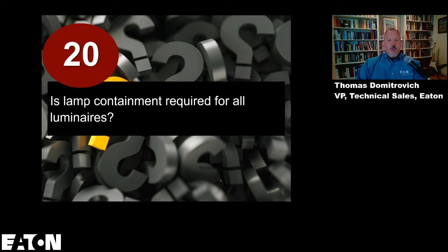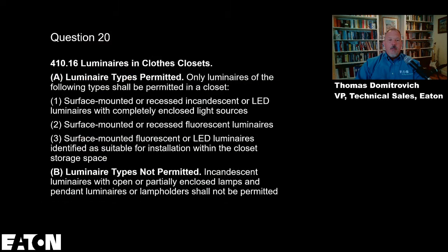And it's not required for all luminaires, but I guess the message is, it depends on where you're applying it, right? The location that it's being applied. If it's in a hazardous location, obviously there are going to be containment issues. If it's in that sporting arena, which is a previous question, there are containment items. If you're in an area where you're near fabric or other ignitable sources or materials, then you're going to have some containment and spacing requirements.